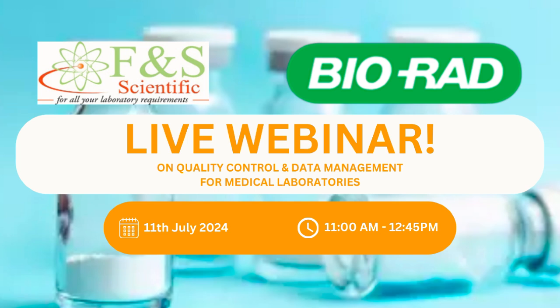There are scenarios where there are no QCs in the market. What alternatives are there to continue testing? Someone is asking for alternatives when you don't have a proper QC in the market. A very good question, Robert. There is something called alternative assessment. Even for EQA, you may not have an EQA program. So when we talk about alternative testing, we mean you get a minimum of at least 3 labs. You do your test, the other person does the test, then you compare your results. The other option is just split testing. For example, I split my samples, it's also called blind testing, among technologists that are analyzing this test, and then they all do that test, and then we look at them.